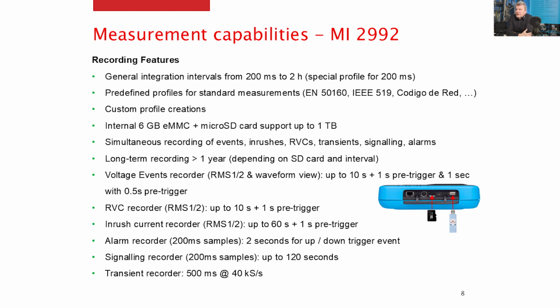We also create specific predefined profiles for standard measurements. For example, 50160, IEEE 519, or specific código de red, which request specific integration periods and specific registers. We specify directly in the profile what is included. For example, for 50160, we specified harmonics up to the 25th, which is requested by the standard, and only 25 is included in the record. But if you create your own profile, you can use the so-called user-defined profile, where you specify directly on the instrument what will be included, what the integration periods will be, and so on. There is also the possibility that with a special tool, the end user will define a custom profile of their own creation.